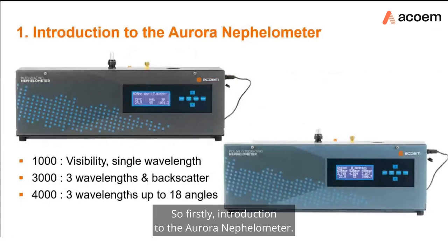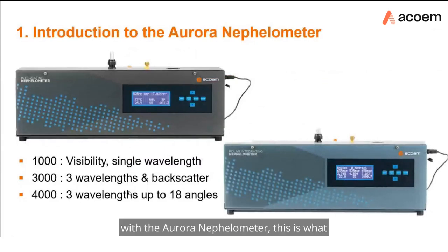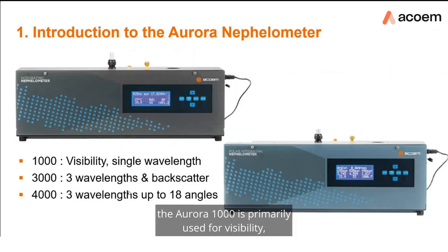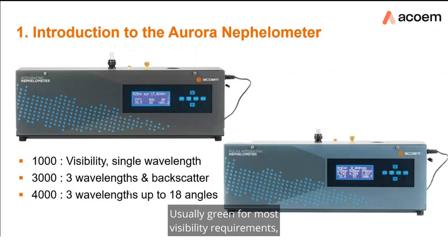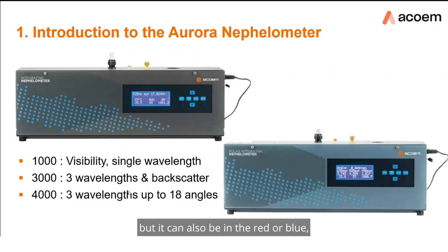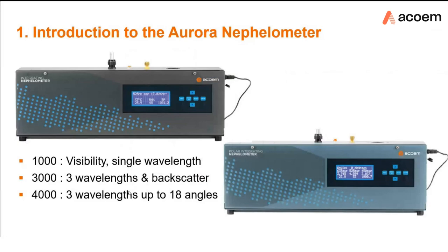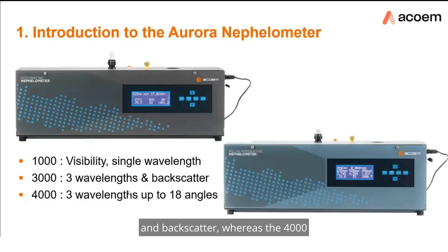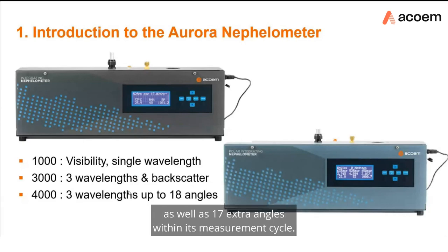The Aurora nephelometer comes in three main variations. The Aurora 1000 is primarily used for visibility, measuring scattering at a single wavelength — usually green for most visibility requirements, but it can also be red or blue. The Aurora 3000 and 4000 are generally used in research applications: the 3000 has three separate wavelengths simultaneously and backscatter, whereas the 4000 adds the ability to have full scatter as well as 17 extra angles within its measurement cycle.